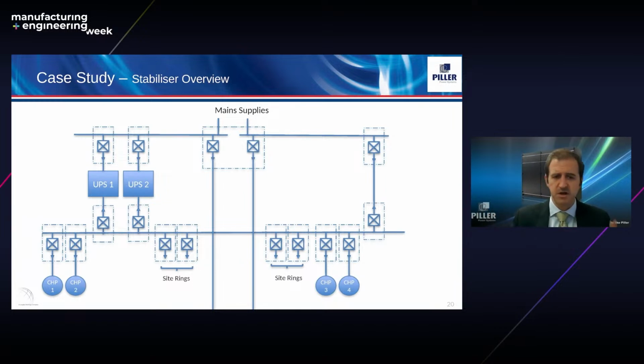The other issue was the DNO restricted the size of their supply, so they had no other choice than to generate their own power. This was also restricted by the fault levels in the local area. The addition of the UPS generator upstream of the generation allowed isolation between the grid and the site. Ultimately, that isolation allowed this whole facility upgrade to go ahead as planned — otherwise it could have been completely thrown out, or required very expensive new connections to the network.